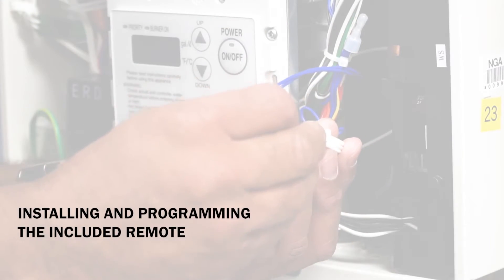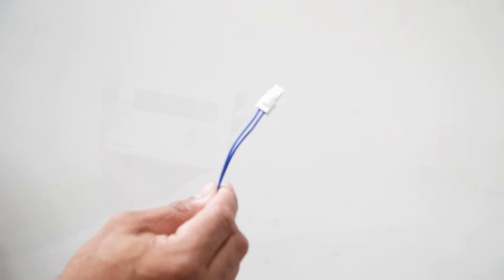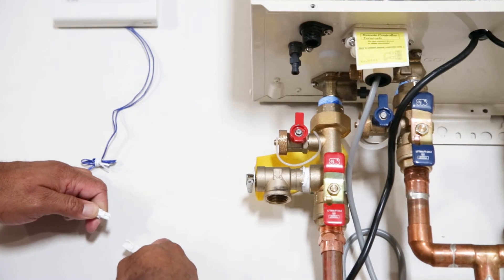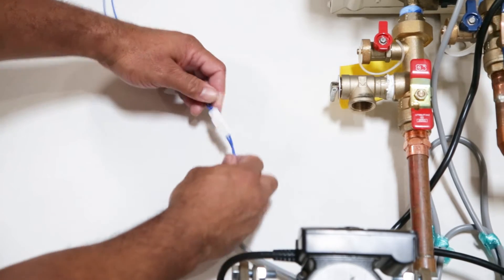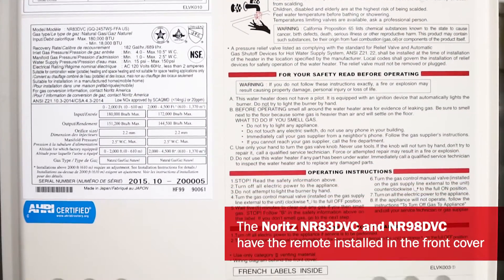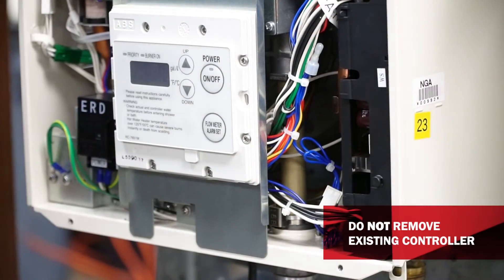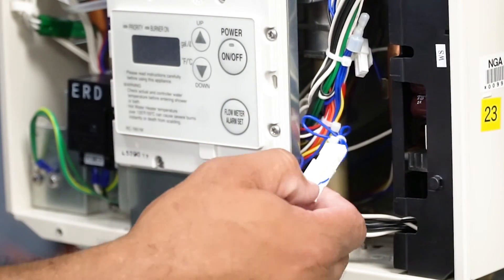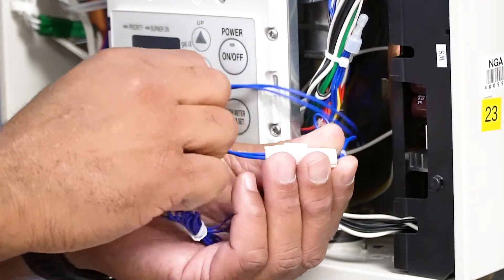Next, we will install the kit's supplied remote. This designated remote is required for programming your recirculation system. Start by disconnecting the heater's existing remote by removing it from the blue wire connector. Connect the newly supplied pump kit remote using the same prior remote wire on the heater. The Noritz NR83DVC and NR98DVC models have the remote installed in the front cover. Do not physically remove this now inactive built-in remote. Disconnect the internal remote wire and feed the new remote wire through the bottom of the heater. Connect the new remote wire to the heater remote wire connection.